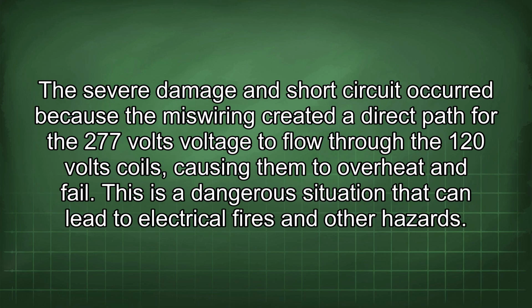The severe damage and short circuit occurred because the miswiring created a direct path for the 277 volts to flow through the 120 volts coils, causing them to overheat and fail. This is a dangerous situation that can lead to electrical fires and other hazards.